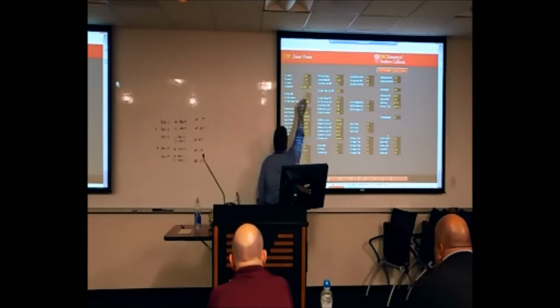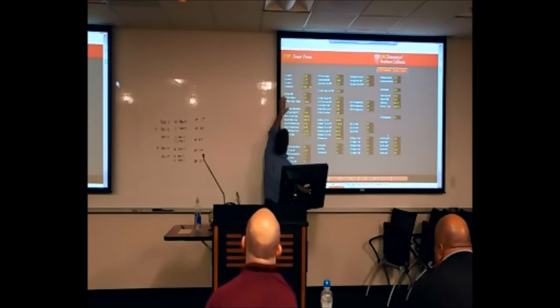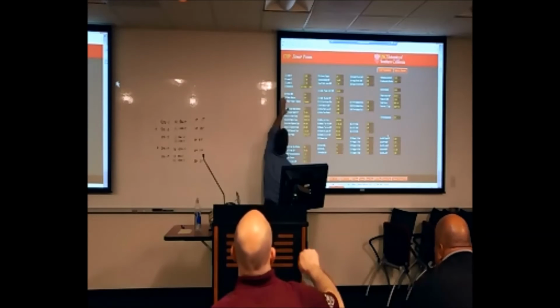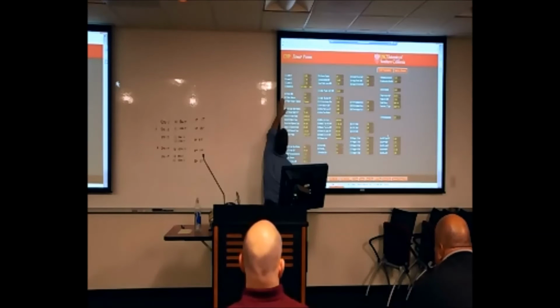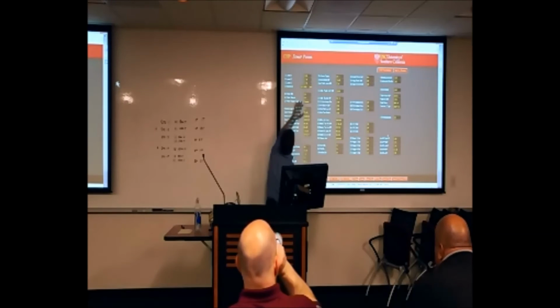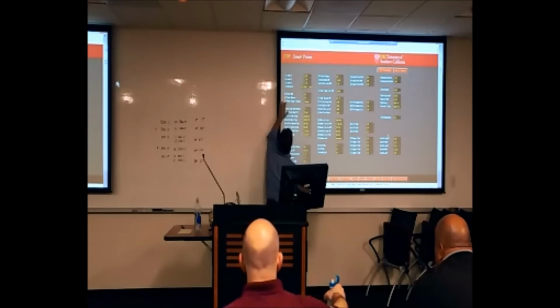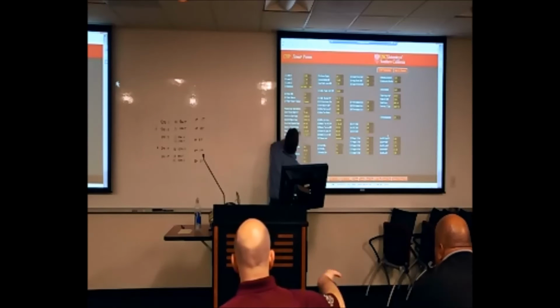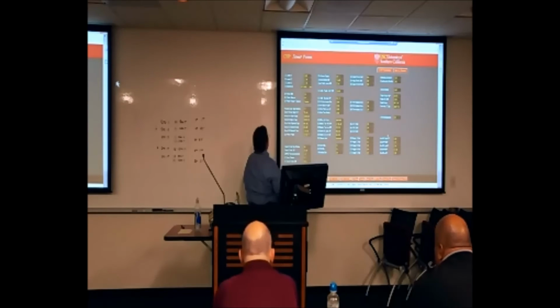Cooling tower level shows up at the top. The cooling tower water makeup again shows up at the top. We have a filter. There's a sand filter out there, and Honeywell does control the filter start-stop on that, and that's controlled by a time schedule. Right now it's 24/7. We have a filter status, and if we have a status mismatch, we indicate an alarm of that filter pump.